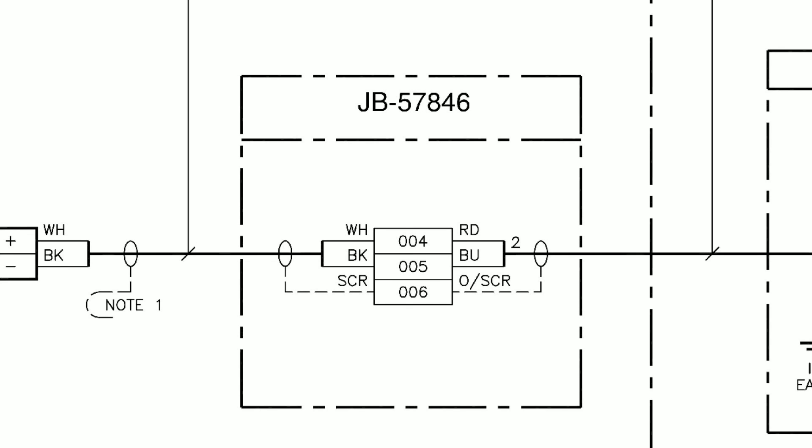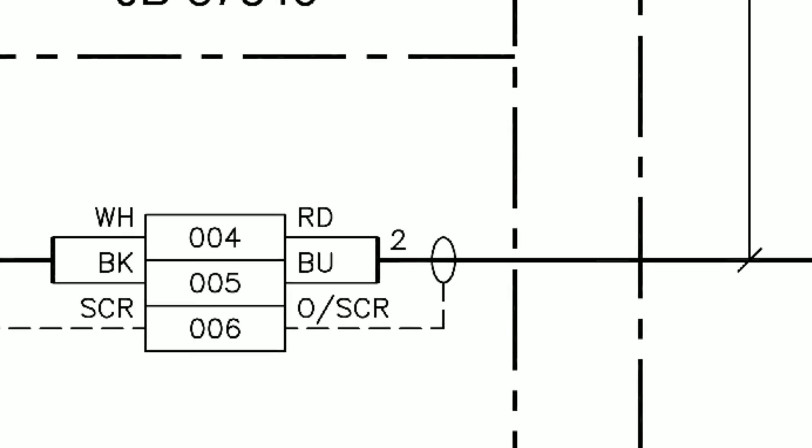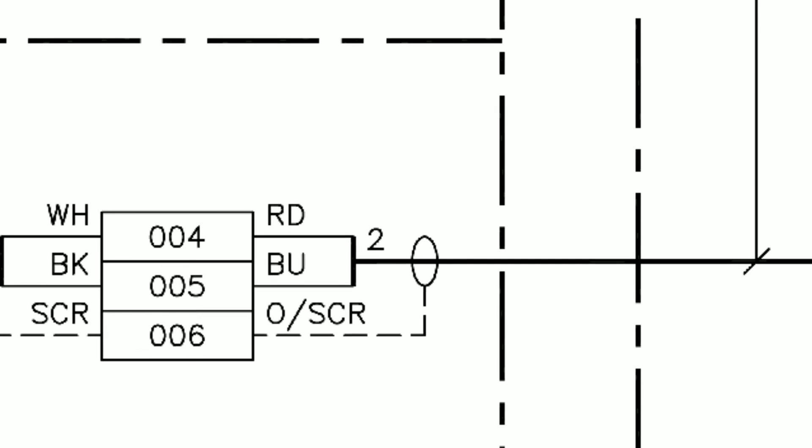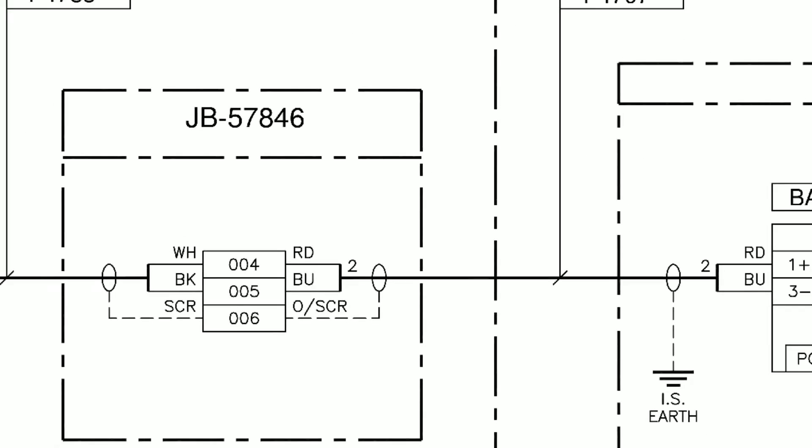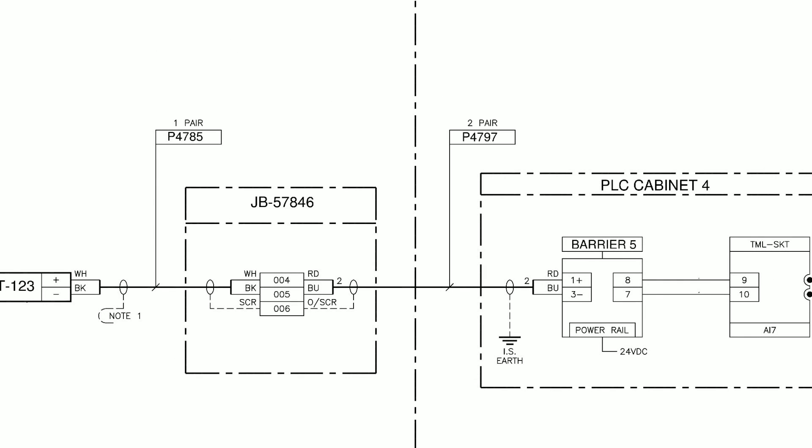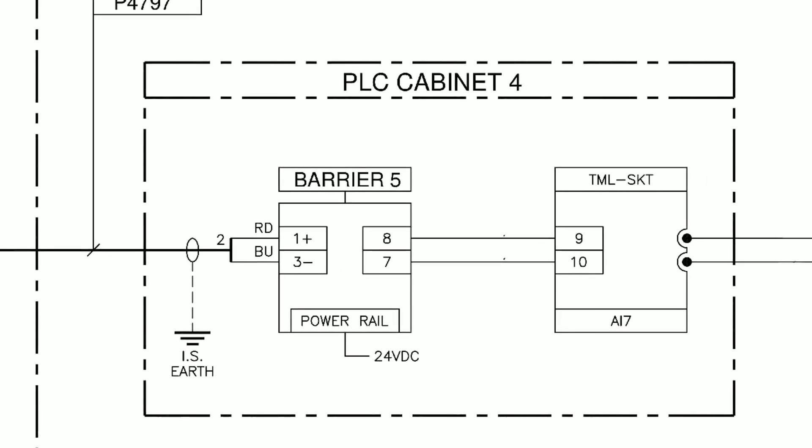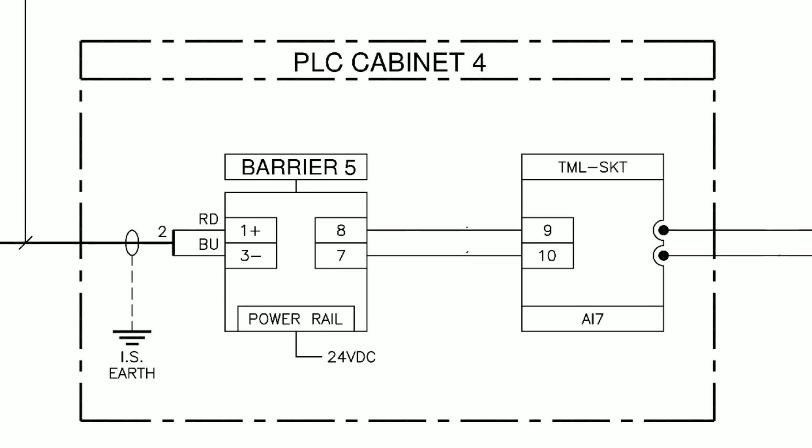If we look closely we can see that this is pair 2 on the two-pair cable. This is denoted by the small 2 next to the terminal connections. We can also see that these cores are coloured red and blue. It's important to note that this two-pair cable spans across the dividing area we spoke about before in the dotted line, showing that the signal is going from the local equipment room and into PLC Cabinet 4.